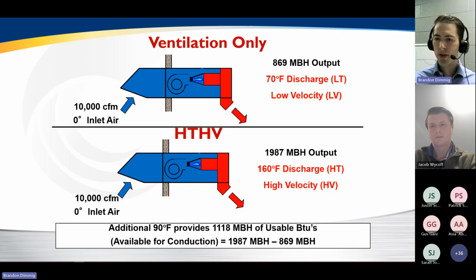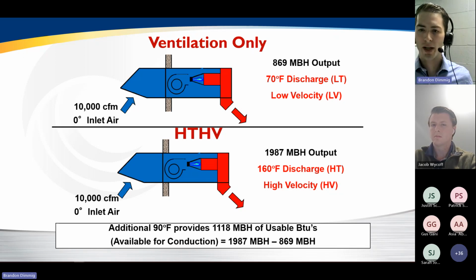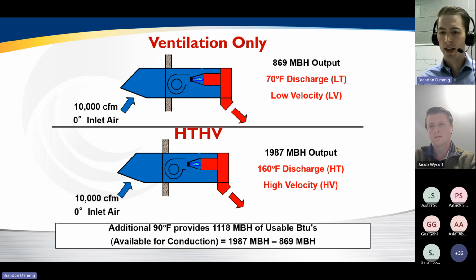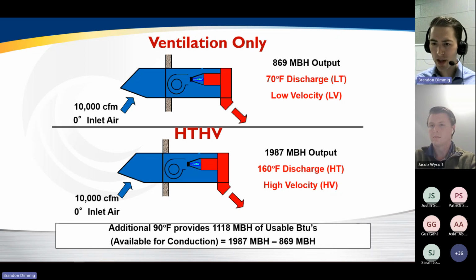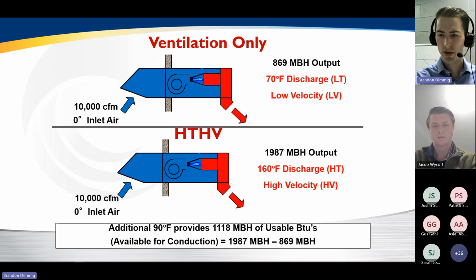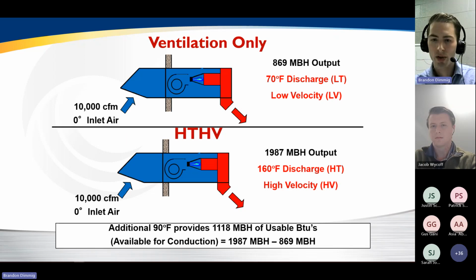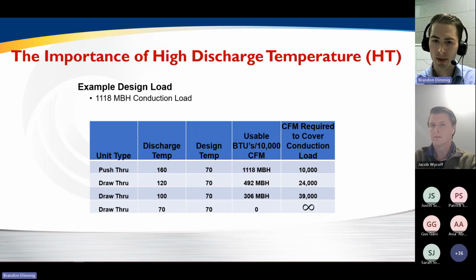Some folks will say, well, a BTU is a BTU. I'm comparing a draw-through unit to a blow-through unit, and I'm meeting this BTU to BTU. But the reality is, if you go one step down and look at the usable BTUs, that number will change between the two. And a blow-through HTHV unit is going to have more usable BTUs to meet the conduction load of the space. If you don't have enough usable BTUs and they don't exceed your conduction load, that's when you can get into conditions in which you're not able to maintain the target internal space temperature.